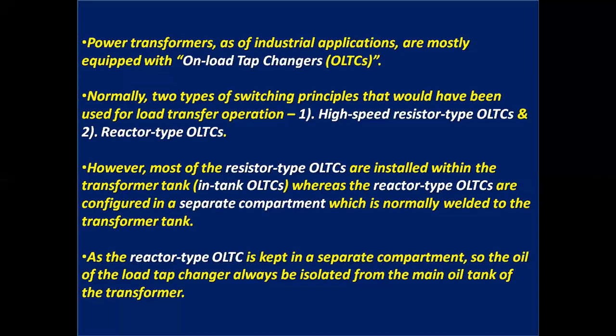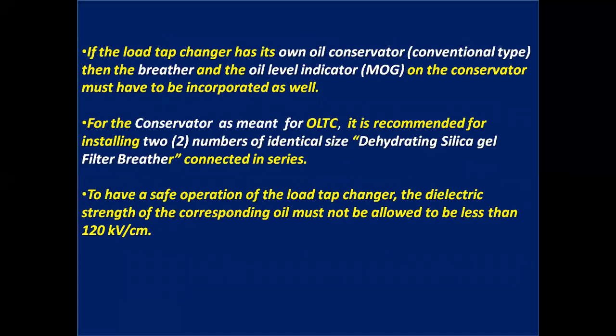As the reactor type OLTC is kept in a separate compartment, so the oil of the load tap changer always be isolated from the main oil tank of the transformer. If the load tap changer has its own oil conservator, conventional type, then the breather and the oil level indicator on the conservator must have to be incorporated as well. For the conservator as meant for OLTC, it is recommended for installing 2 numbers of identical size dehydrating silica gel filter breather connected in series. To have a safe operation of the load tap changer, the dielectric strength of the corresponding oil must not be allowed to be less than 120 kV per centimeter.